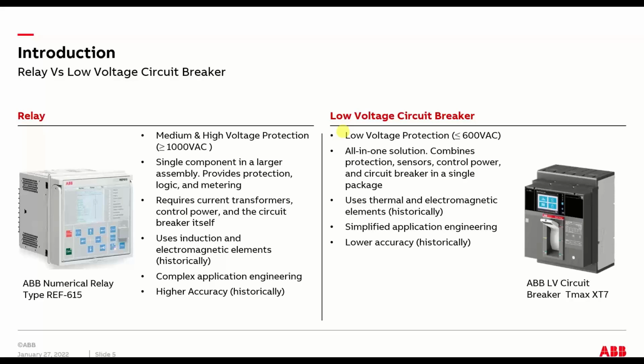But so, the relay versus circuit breaker: relay for medium voltage, the molded case circuit breaker, and low voltage circuit breaker for under 600 volt applications. The big difference is that the relay is one component in a larger engineered system, whereas the low voltage breaker is an all-in-one solution, basically pre-engineered. I don't like to say plug and play, because there's still a lot of engineering that goes into it, but it's a solution where you pick up your breaker, and all its ratings and everything are pretty much predefined, and all the parts you need are included in the package that you buy.